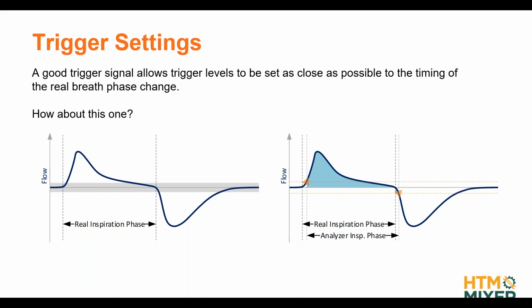However, a little drawback here is, as you can see, it's all shifted a little bit in timing. So this means that our timing-based parameters like a frequency or an I/E ratio will still be accurate because it's just a little bit delayed, but overall it's pretty much the same, right? But beware that in situations like this, we have the same little problem that we discussed in our first slide with the trigger settings that were a little bit off, right? So here the volume is the area underneath the curve on the waveform. Here we are missing a little bit of volume, and here we are counting a little bit of our expiratory phase as inspiratory tidal volume. So it is a good trigger signal, but it would be even better if we had a little bit steeper slopes of our signal here. Then even our tidal volume calculation could be more accurate.